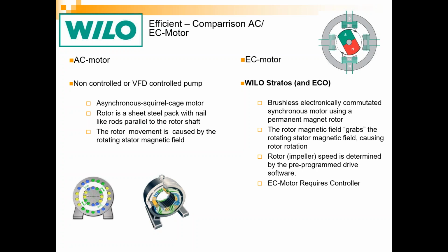Wilo was the first company to put electronically commutated motors in the pumps more than 20 years ago. We at DB Sales have been selling this for over 10 years. We have a lot of field experience with electronically commutated motors being used in pumping applications. And we've seen a lot of systems that may have air and dirt separators on them, but they're not pulling out ferrous material because they didn't have any type of magnetic separation. Well, that ferrous material ends up in this pump, and it's not good for the pump.